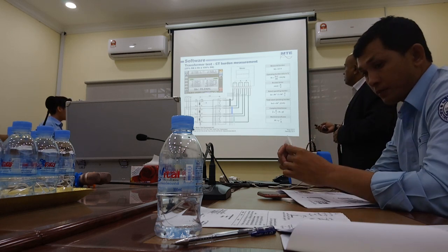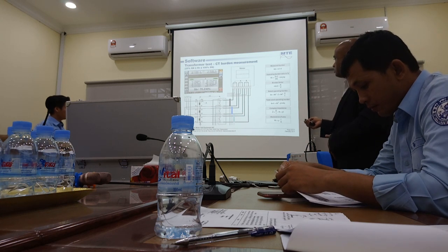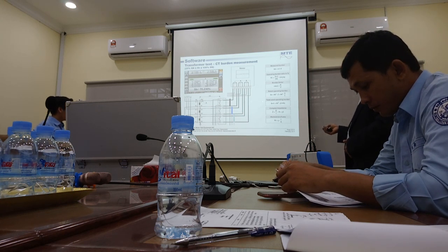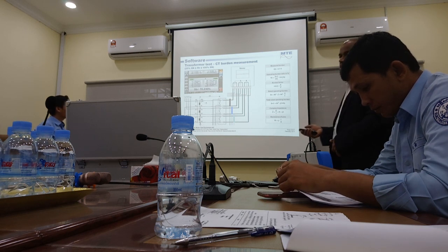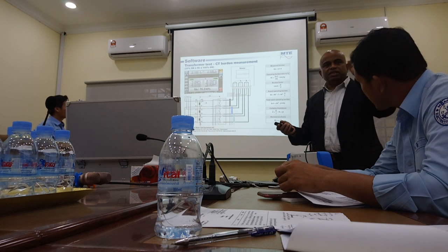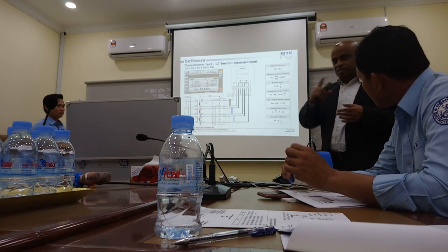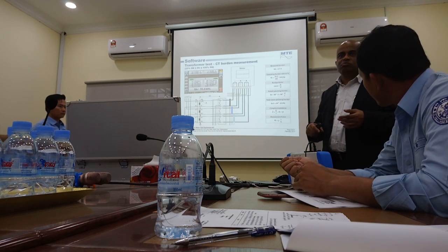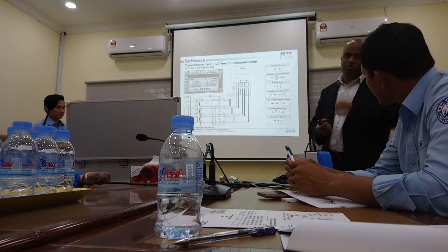Okay, similarly you can do CT. CT is more simple to understand. Okay. So what is CT? Basically, what can contribute to the CT burden? It is your connection wiring. Maybe loose contact. It is not crimped properly. Your wire diameter is smaller.